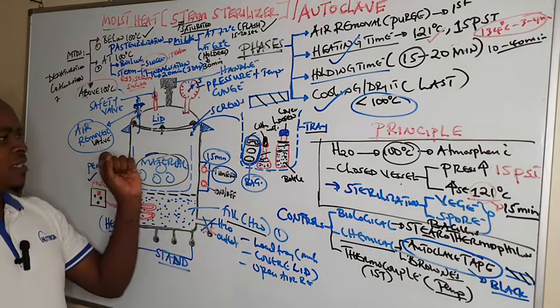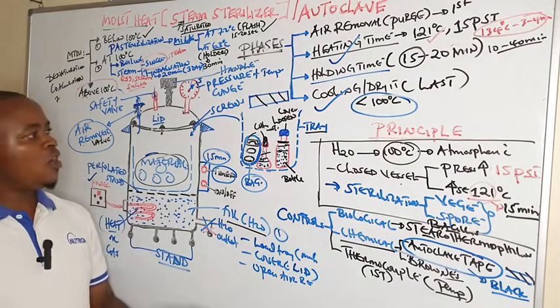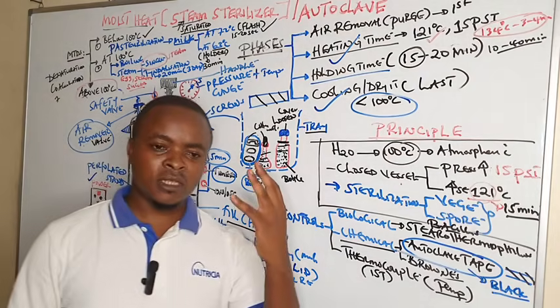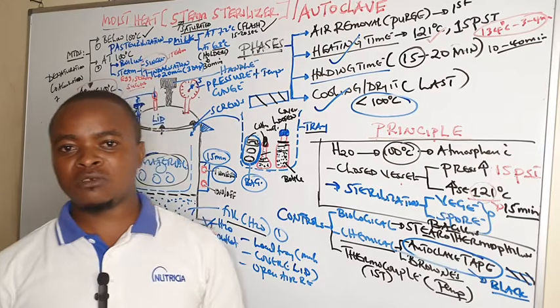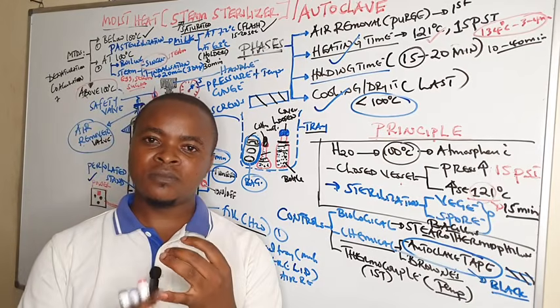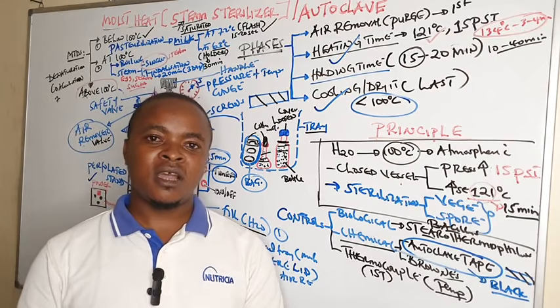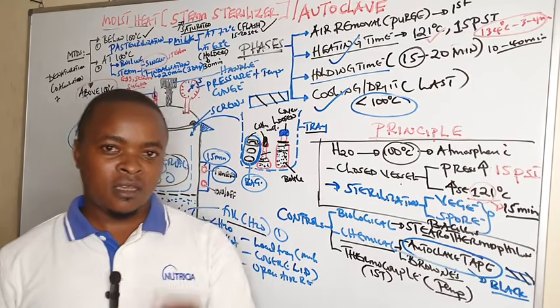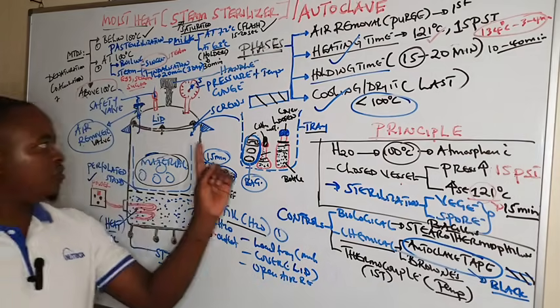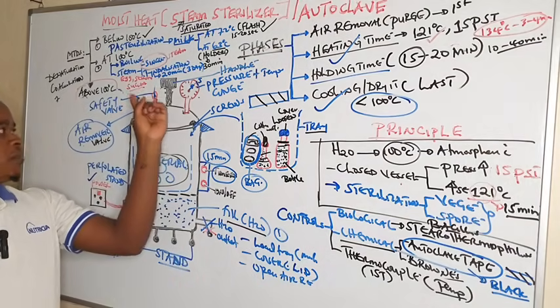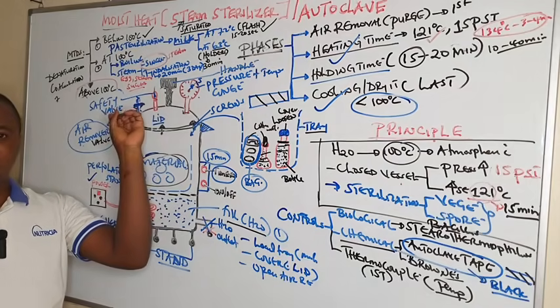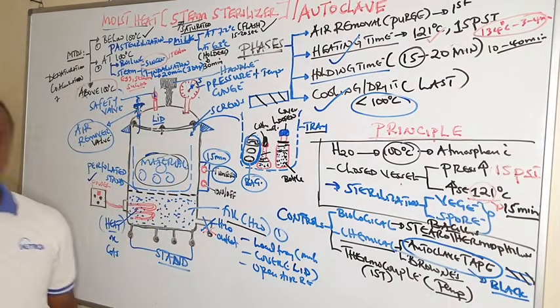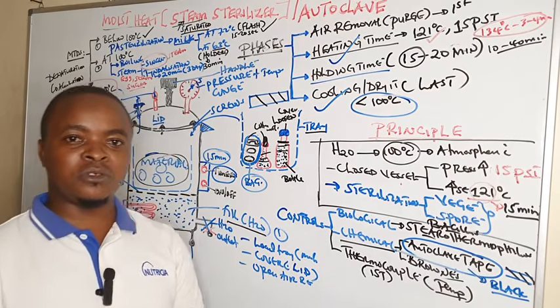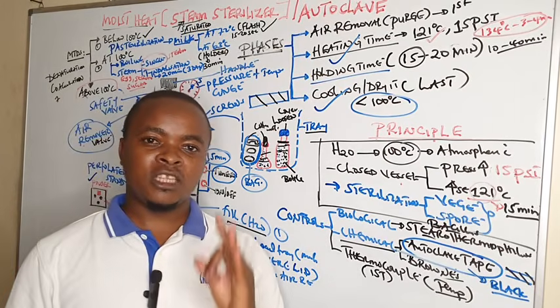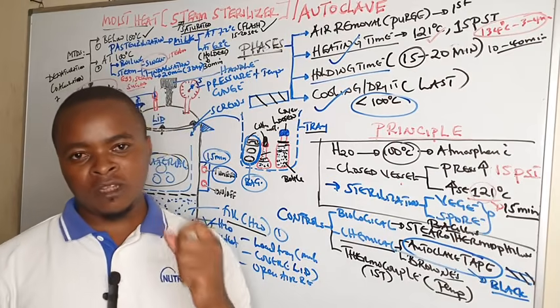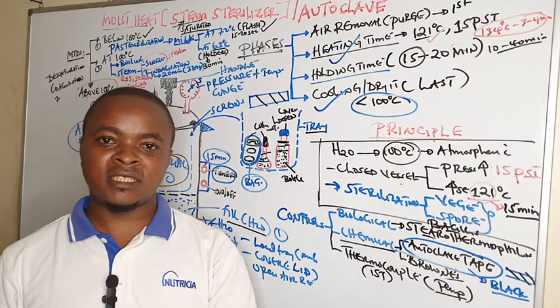So this is what we can discuss with you in this session. What are the factors that affect maximum sterilization by autoclave? One is time, another one is pressure, another one is the air. If you have not allowed air to be removed by forgetting to open the air remover valve, it can affect sterilization, also the time you use, and also the pressure at which it is being maintained. Those three factors affect the sterilization.